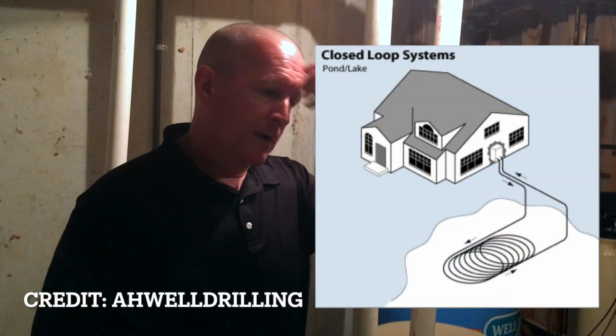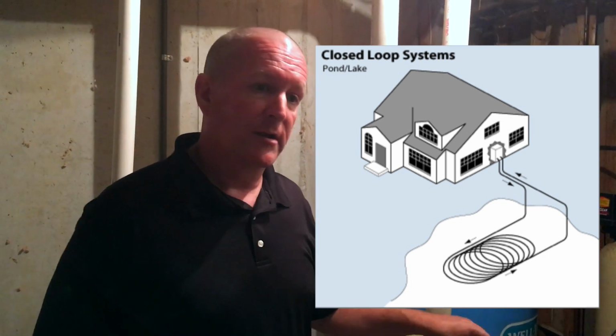Okay, so geothermal systems, you have to have some source, a ground source. Most of them, when installed these days, are what's called a closed loop. They dig a big long trench, zigzag back and forth, and bury flexible plastic pipe in it, running a water and glycol solution through it. It dumps heat to the soil or picks up heat from the soil. That's called a closed loop system.